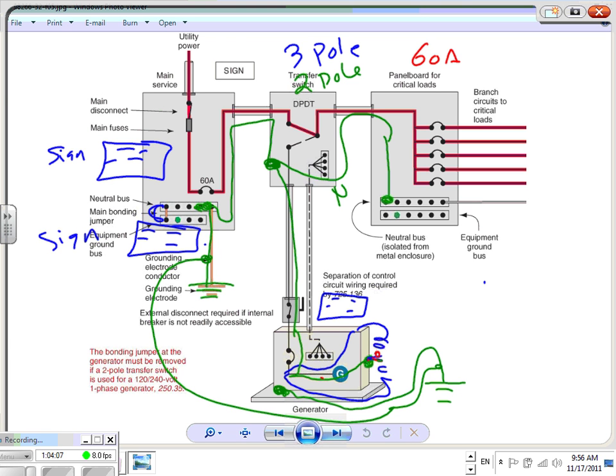Thinking, well, this panel is dead, I de-energize it from here, not knowing that this system is still running on the generator. Well, who cares? I'm not into this system. But your neutral here is grounded right at the panel. So in 2011, the code discovered that somebody could be zapped really good if anybody tampers with the grounding electrode conductor. Not tamper, just maintaining, if you maintain it, disconnect it, work on it.